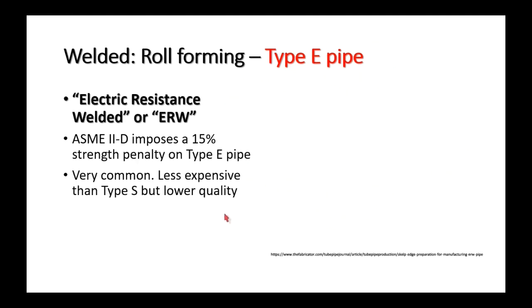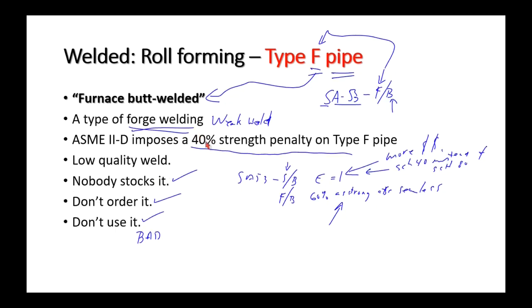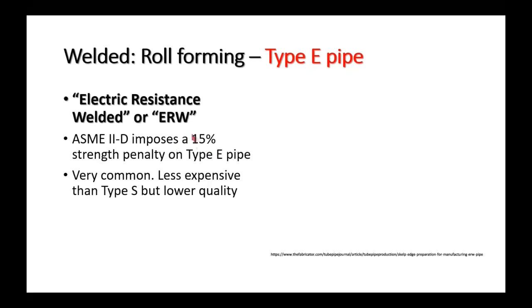ERW — electric resistance welded pipe — is in the middle: instead of a 40% strength penalty like furnace butt weld, it gets a 15% strength penalty. It's less expensive than Type S seamless, lower quality, but very common.